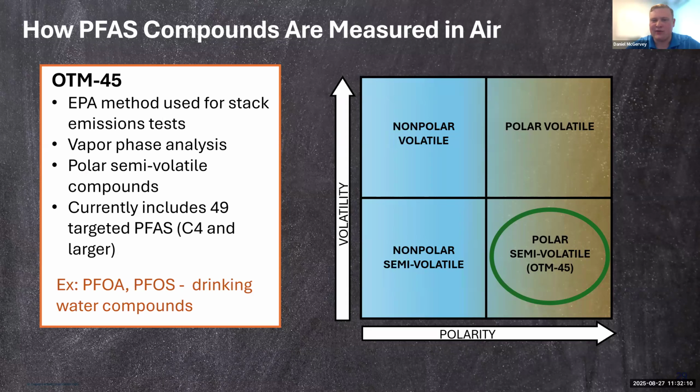Now, in air, there is a specific method for PFAS compounds to be measured. There are different methods for different phases of testing. If you're looking at a solid phase, liquid phase, or gas phase, there are different types of tests to detect PFAS, but air is a little more novel and comes with a few others that I won't get into today. This is the main EPA method used for the stack emissions test. So this is where the main destruction removal efficiency we want to look at is, out of that final exhaust stack.